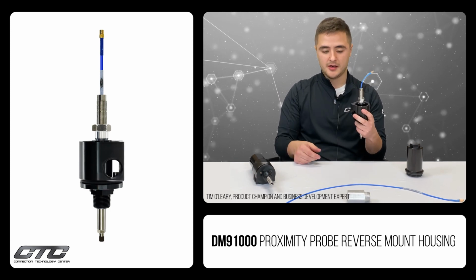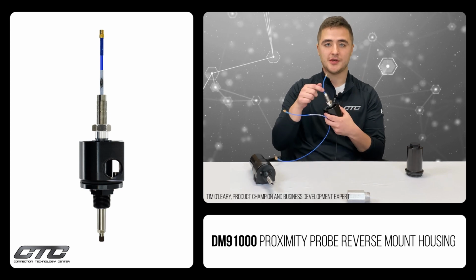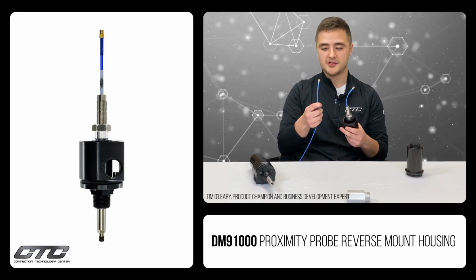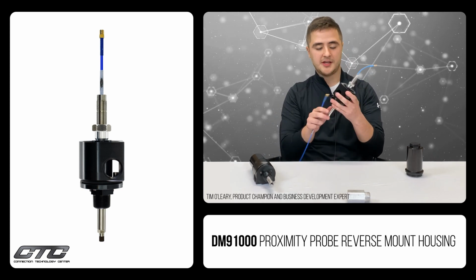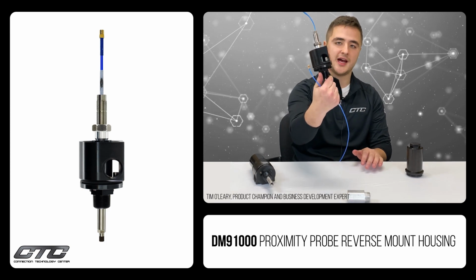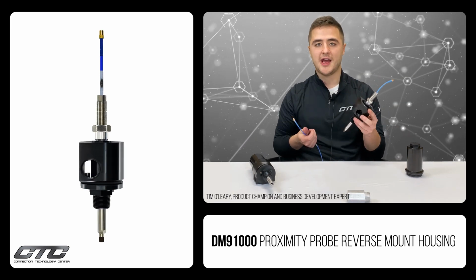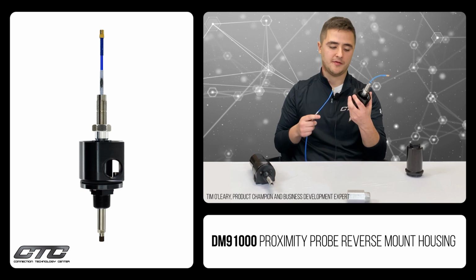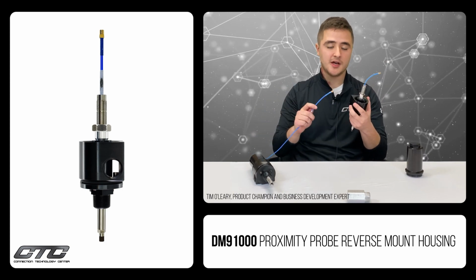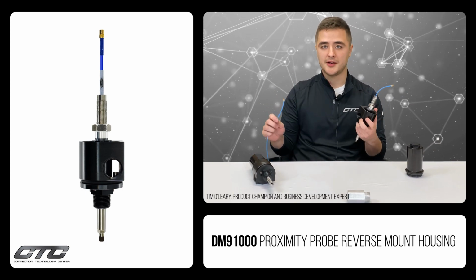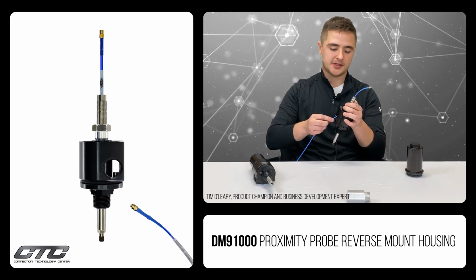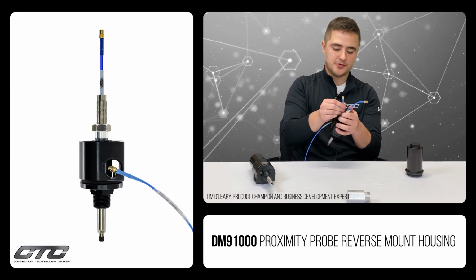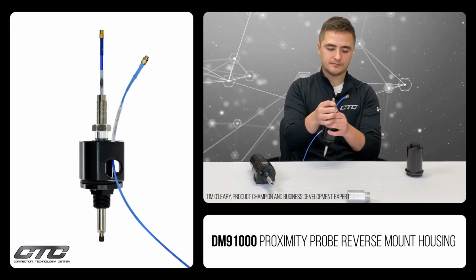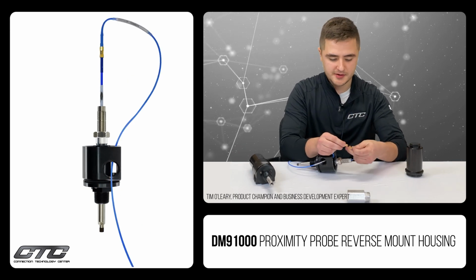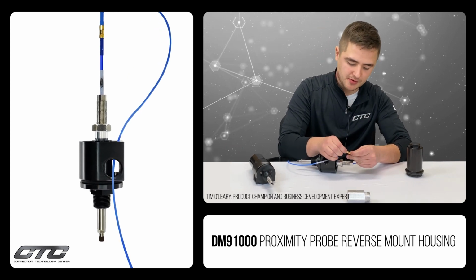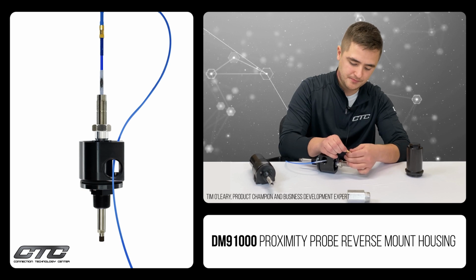After that, you need to make the connection between your proximity probe and your extension cable. Right here you can see on both sides of the reverse mount housing we have 3/4 by 14 NPT fittings, so these can be run through conduit. We'll take the extension cable, thread it through that NPT hole. From here, you'll make the connection between the proximity probe and the extension cable.